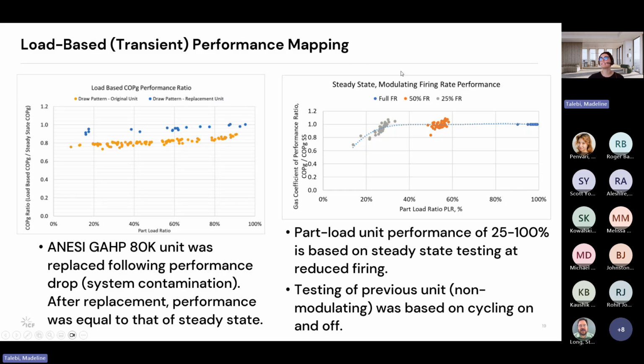And then looking at the steady state modulating firing rate as a function of the part load ratio. The part load ratio, or part load unit performance, of 25 to 100% is ultimately based on the steady state testing at reduced firing rate. And then the testing of the previous unit, the non-modulating one, the previous unit being the Robur. I mentioned I might touch on this later on in the presentation. The biggest difference between the ANESI and the Robur, which was the GHP #1 testing, and we had to navigate with the Robur, is that there are no modulating capabilities on the Robur. It's either on or it's off. It's either firing or it's not. So with the ANESI unit, we had to slightly shift how we were going to test this to try to draw a comparison.